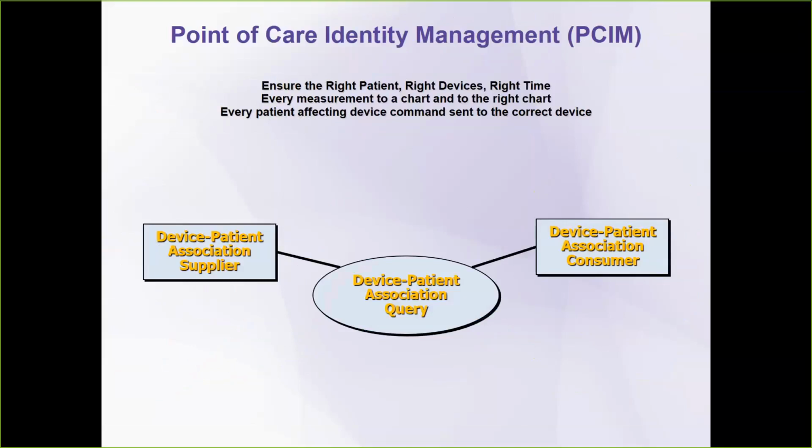And our last profile that we'll cover here is PCIM. The purpose of PCIM is to drive additional use cases and means for recording events from devices as they are associated with the patients. So this is a profile allowing systems to receive notifications of programming events as well as to query the state of patient device associations when needed. The profile creates a single authoritative source for patient device associations using 3 actors.